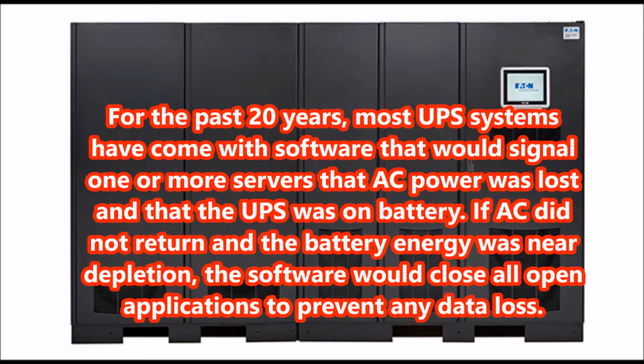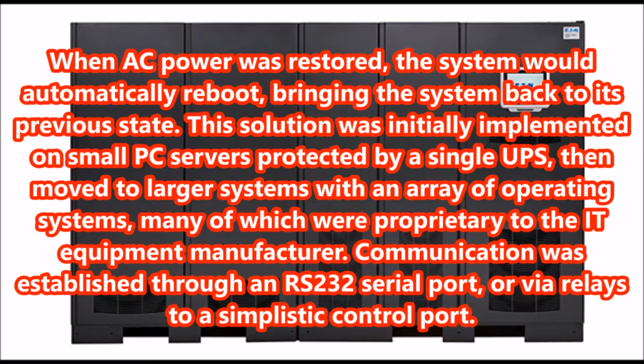For the past 20 years, most UPS systems have come with software that would signal one or more servers that AC power was lost and that the UPS was on battery. If AC did not return and the battery energy was near depletion, the software would close all open applications to prevent any data loss. When AC power was restored, the system would automatically reboot, bringing the system back to its previous state. This solution was initially implemented on small PC servers protected by a single UPS, then moved to larger systems with an array of operating systems, many of which were proprietary to the IT equipment manufacturer. Communication was established through an RS-232 serial port, or via relays to a simplistic control port.